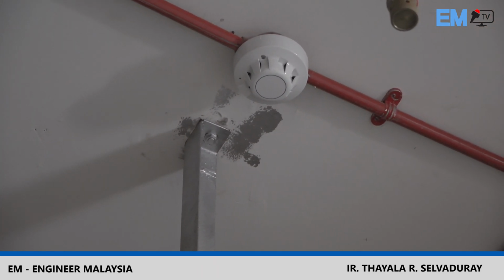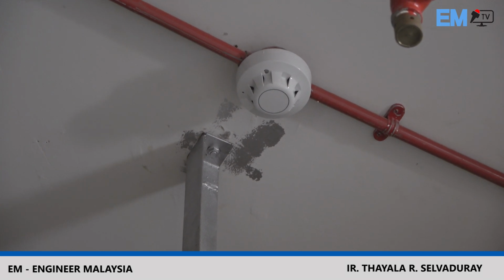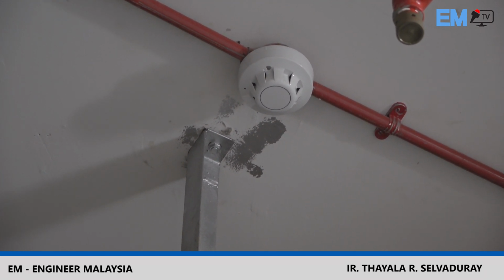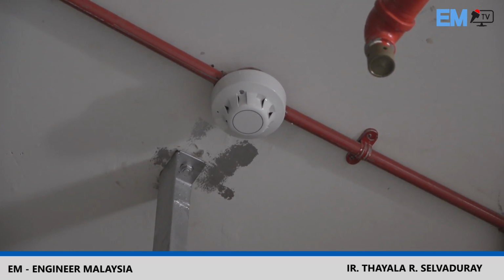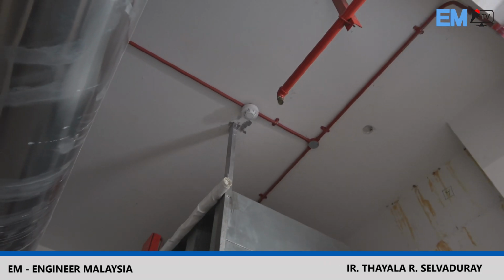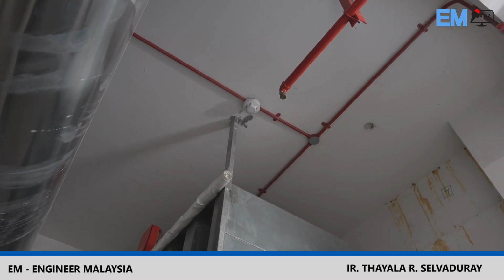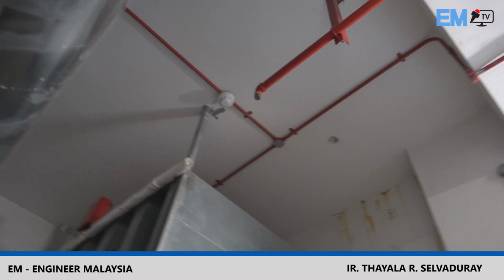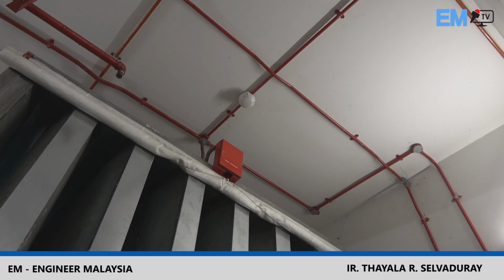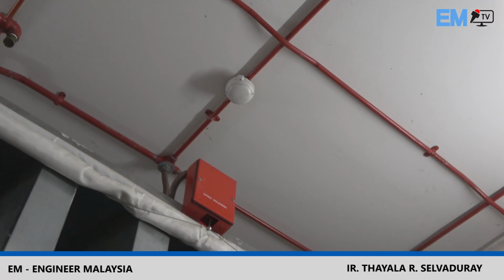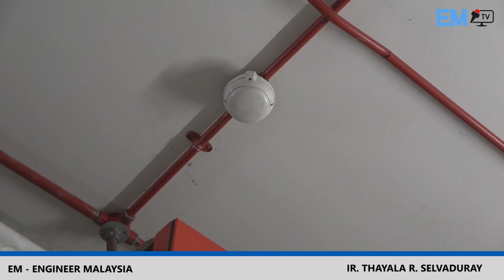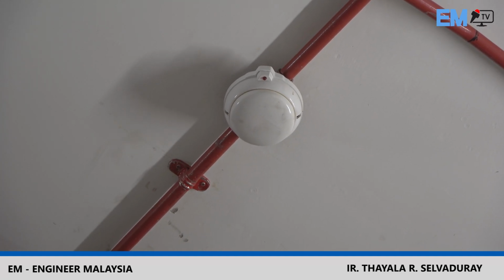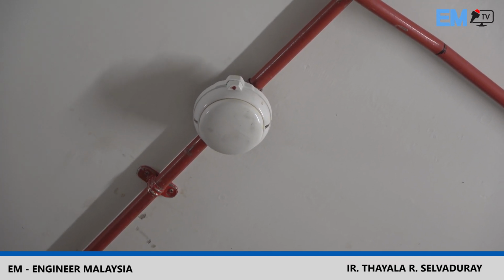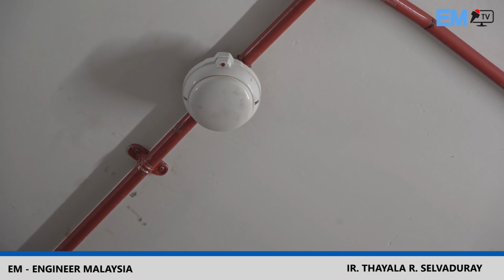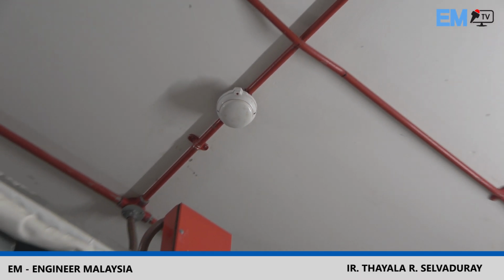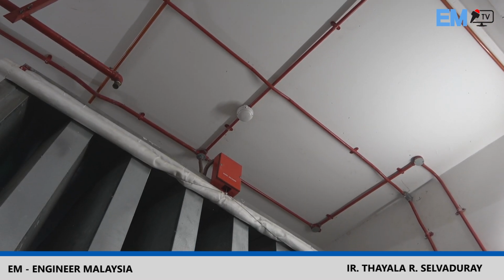In the unlikely situation of a fire, of course smoke will be there first, so that is being picked up. Now, to energize the alarm, it doesn't activate on just one sensor, it has to have more than one sensor, in this case 2 sensors, to ensure that it's really smoke and not a false alarm. So I'll take you to the other one. You see that white dome now? That's the heat sensor. So when it gets hot, a temperature is set to it, and then that will activate. So in the situation where smoke is picked up and heat is picked up, that means it's genuine. If it's genuine, an alarm is sent to the panel I showed you earlier. They call it the fire alarm panel, and within about 30 seconds the alarm will ring.